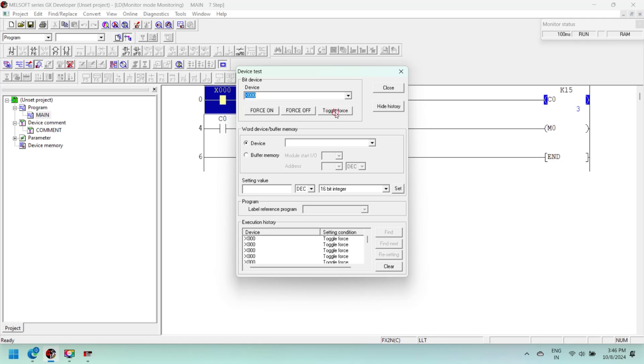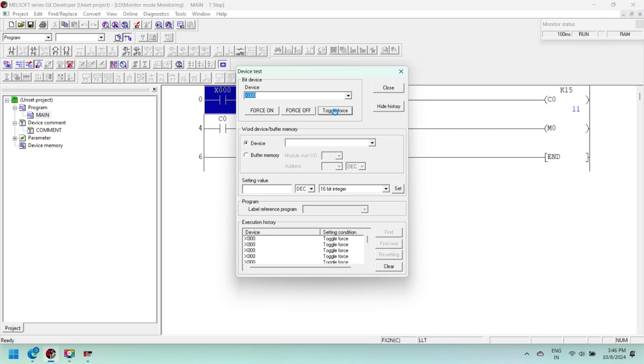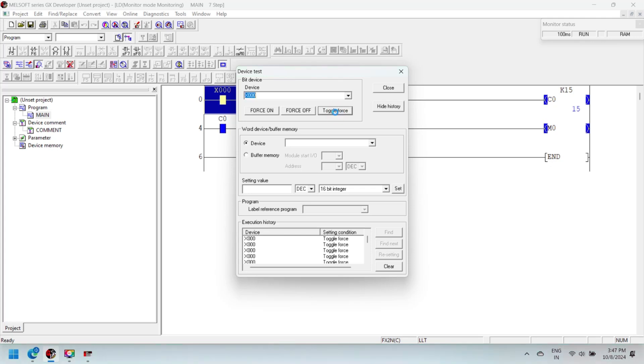The counter value increments when X000 changes from off to on. Each change of X000 increments the counter current value by 1 until it reaches the counter preset value. Once the counter current value reaches the preset value, the counter C0 bit is set to on, which sets M0 to on.